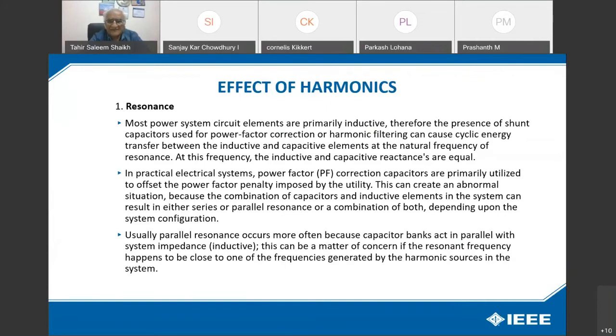This can create an abnormal situation because the combination of the capacitors and inductive elements in the system can result in either series or parallel resonance or a combination of both, depending upon the system configuration. Usually, parallel resonance occurs more often because capacitor banks are in parallel with system impedance inductive. This can be a matter of concern if the resonant frequency happens to be close to one of the frequencies generated by the harmonic sources in the system.